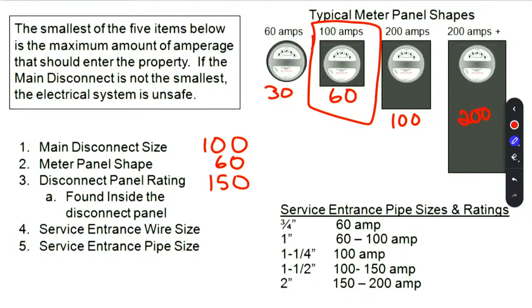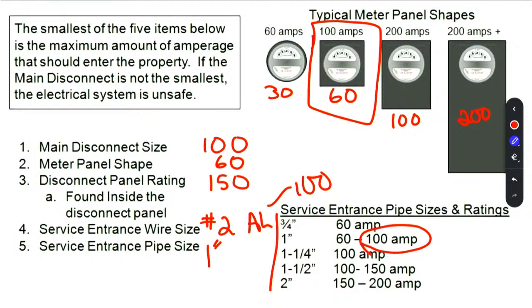Comes in there. The service entrance wire size, we should have those memorized. Let's just say it was a number 2 aluminum that came into the house, which is a very common feed. A number 2 aluminum in this area is good for 100 amps. And then the service entrance pipe size, that's what this charge, this is accurate, this is a science. Let's say this is a 1 inch and we're showing that it can go up to 100 amps.